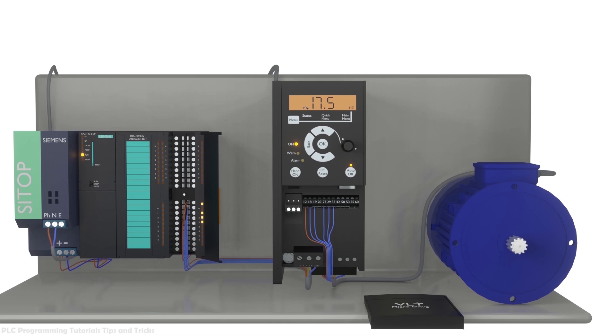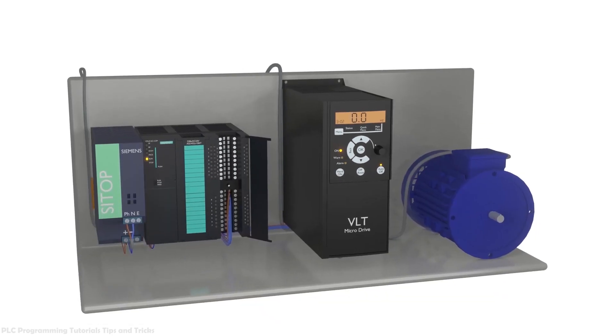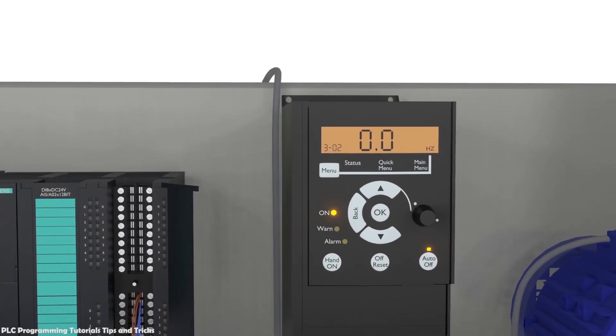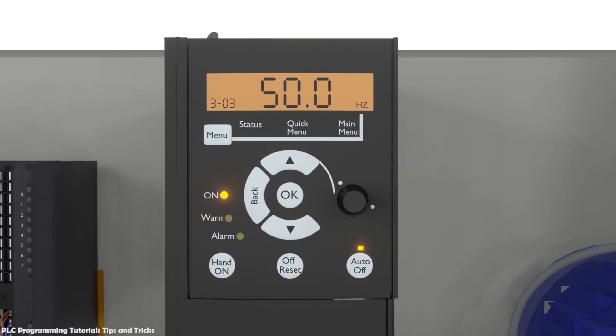Let's start today's session by setting some parameters in the VFD. We are using the FC51 Danfoss VFD in today's tutorial. First we will set parameter 3-02 to 0.0 Hz — this is the minimum output frequency of the VFD. Next we will change parameter 3-03 to 50 Hz — this is the maximum output frequency of the VFD.